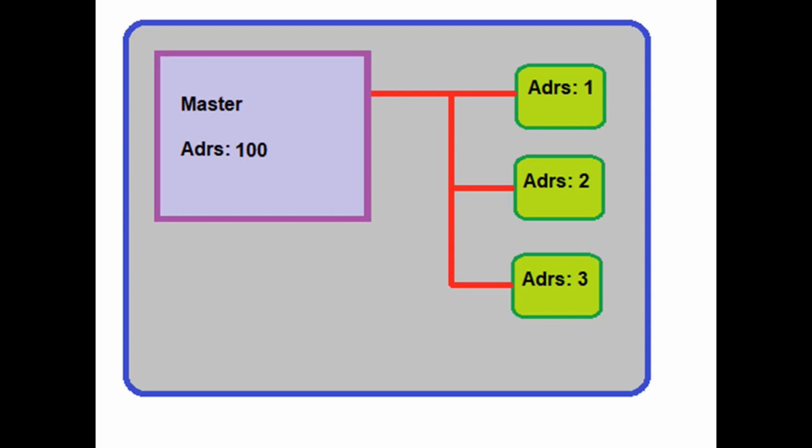Addresses for outstations need to be unique for outstations on the same serial communication line. Messages sent by a master on a serial line are detected by all outstations on that line. The DNP3 address provides a method for each outstation to identify a message as belonging to them. It does not matter what the address is, as long as no 2 devices have the same address.